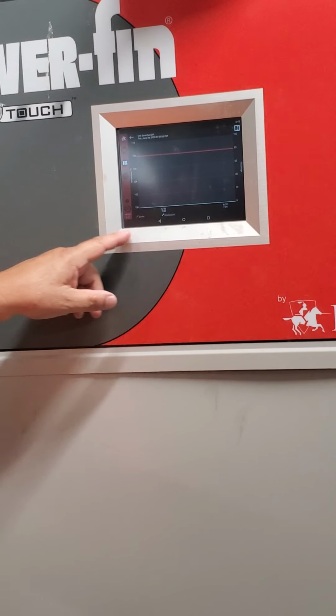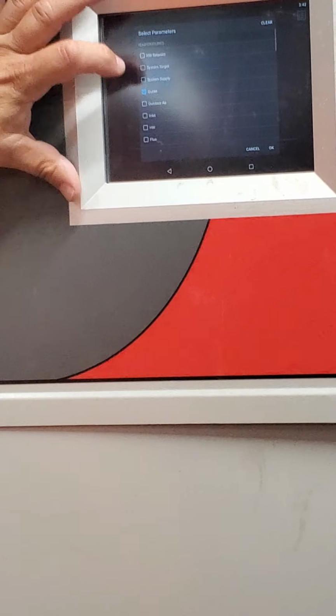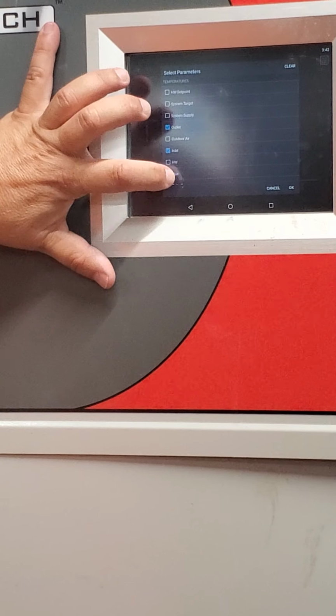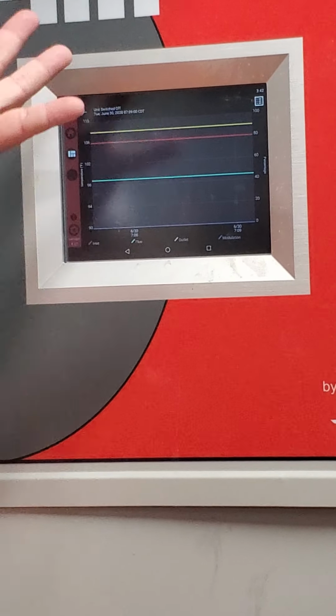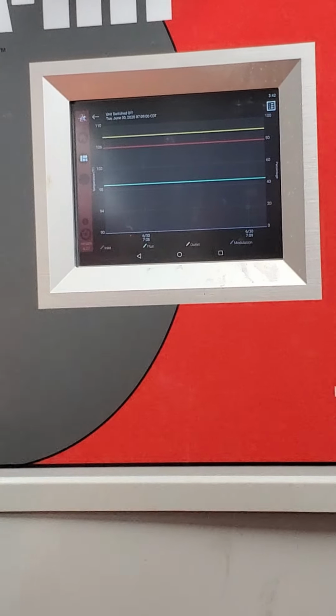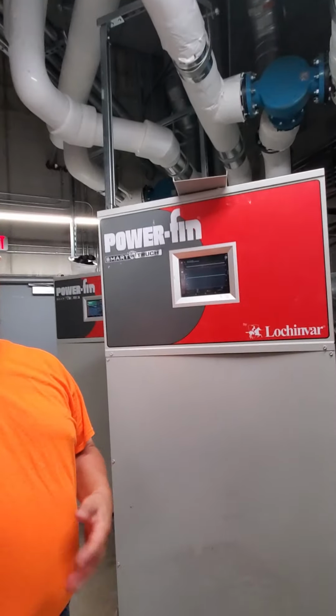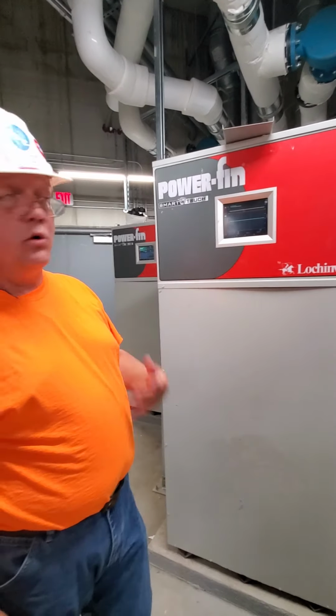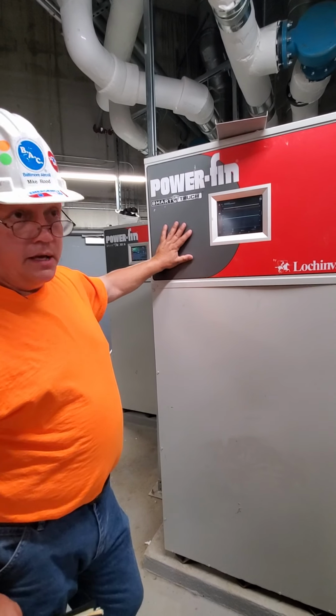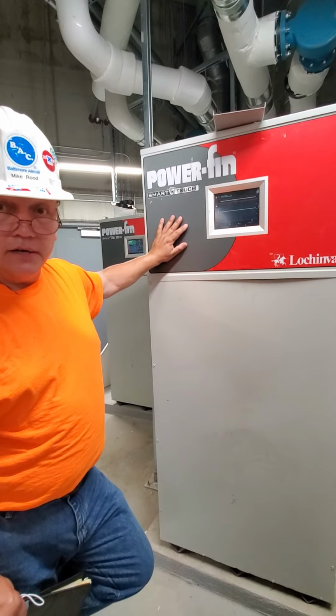And it'll time out and give you a graph of information. You can select, find out what modulation it was at when it failed. You press that and you can select numerous things to see what it failed, when it failed. Press OK. It's timing back out. That information will pop up and it gives you data on both sides to see exactly what the conditions were when it did fail, so to help you troubleshoot it and get the problem resolved a whole lot quicker. All the manuals for these boilers are available online at lochinvar.com.